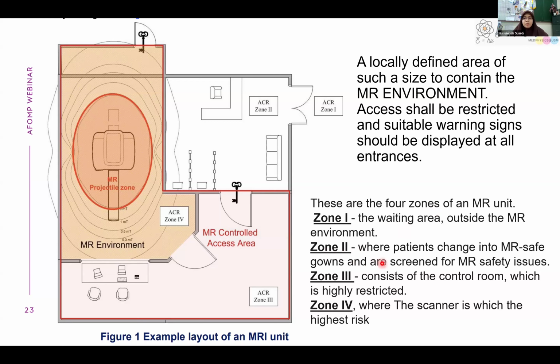Then you have zone 2, where the patients change into MRI safe gowns and are screened for MRI safety issues, because it's important to make sure that the patient does not carry any metals in their body. So this is where you screen them. Then zone 3 is considered the control zone, which is highly restricted and only meant for authorized personnel. And the last one is where the scanner is, which is where the highest risk is.